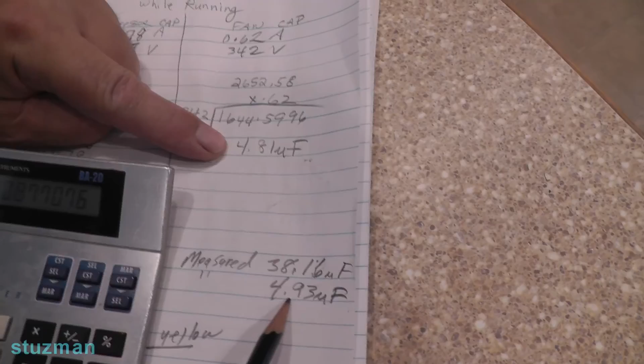So there is a way to measure capacitance while your unit is running. Save you a little bit of time. You can go out there and spot check your capacitors maybe once a year to see if they're still in spec. Now I'm still in spec, but I was getting a little bit low on my 40 microfarads, so I'm going to go ahead and order a capacitor to bring that capacitance up for the compressor.